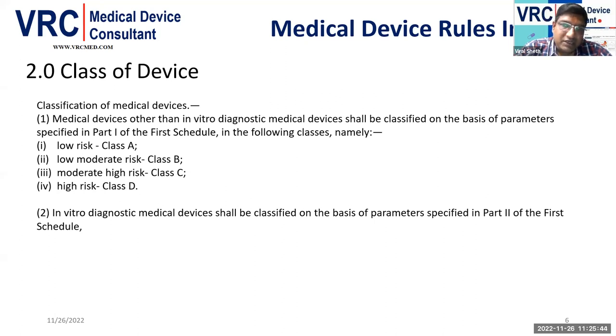You can see that for the medical device that comes in contact with the patient, the risk is there. When we say class A, the risk to the patient made by the device may be very low and may not affect patient health. Whereas for high risk classes, class C and class D, the performance of the device may affect patient health. Hence stringent controls are required, and the rules and schedules are made in a way that indirectly secures the patient's health.